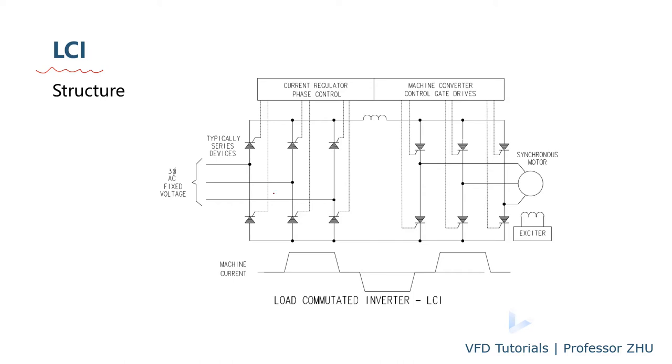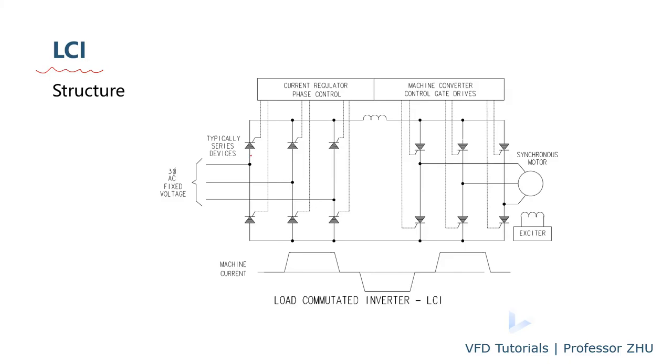And on the rectifier side, also using SCR, the power factor will be very low at low power output. If the motor is running at a very low frequency, the load is very low. And because of the firing angle, the phase angle of the rectifier SCR, the current on the input is lagging the voltage with a very large degree of lagging. So power factor is very low.